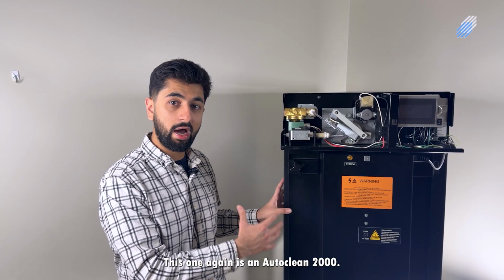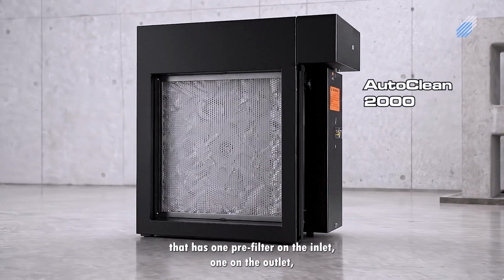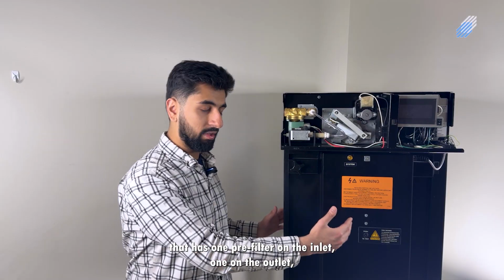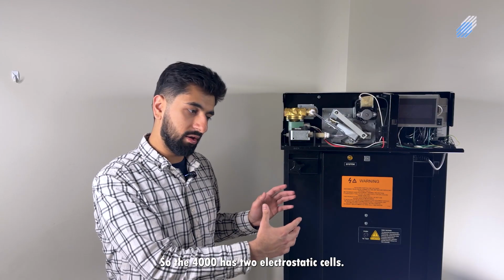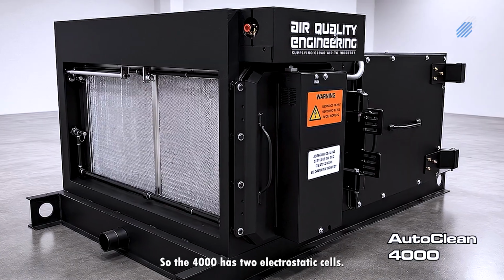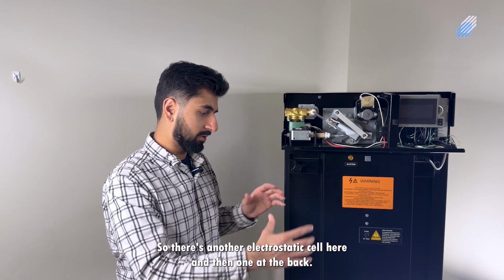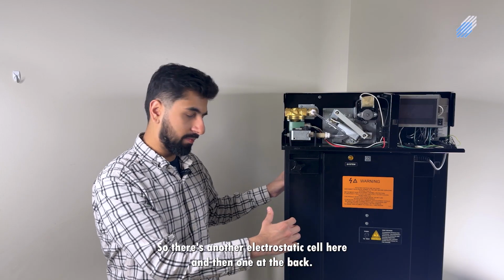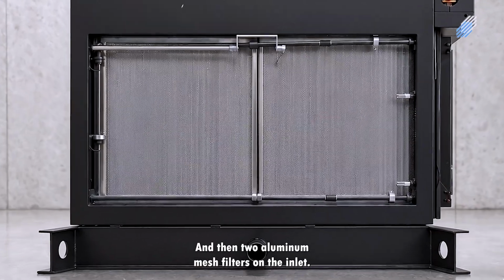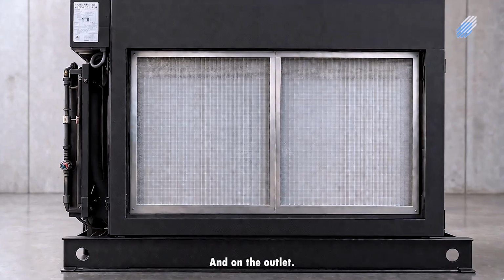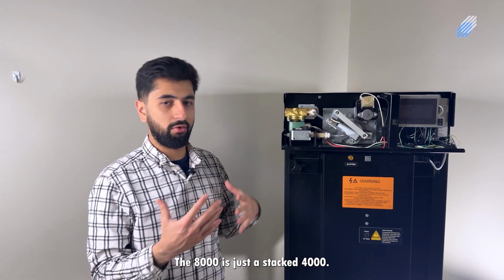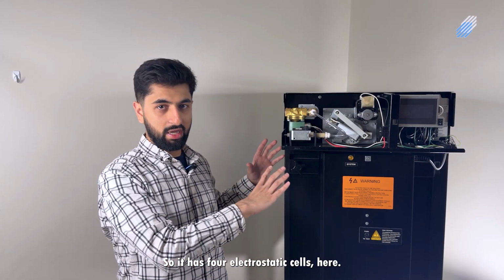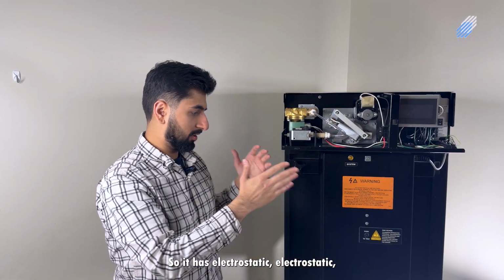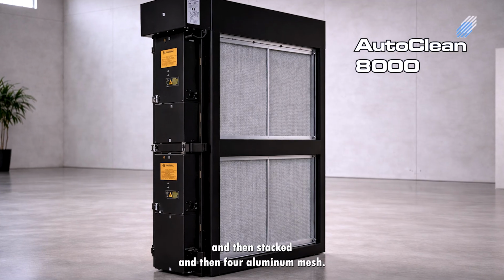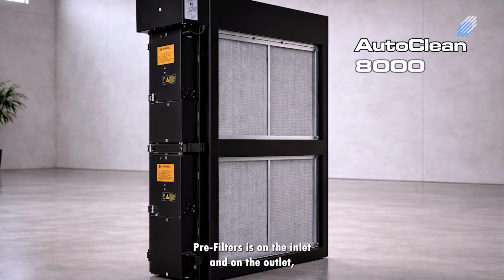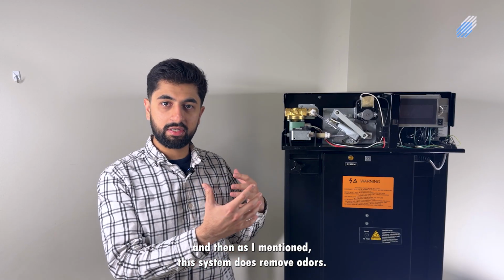This one, again, is an Autoclean 2000 that has one pre-filter on the inlet, one on the outlet, and then one electrostatic cell. The 4000 has 2 electrostatic cells, so it's twice as wide. So there's another electrostatic cell here, and then one at the back, and then 2 aluminum mesh filters on the inlet and on the outlet. The 8000 is just a stacked 4000. So it has 4 electrostatic cells here, and then 4 aluminum mesh pre-filters on the inlet and on the outlet. And then as I mentioned, this system does remove odors.